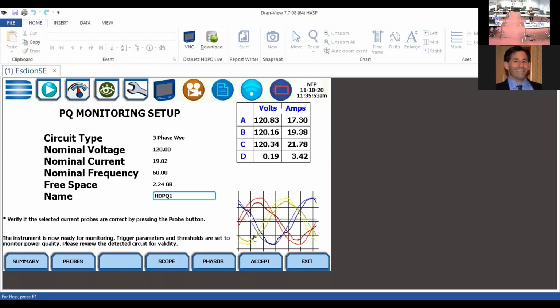And of course, there's another way as well — you can use the phasor display. If I click on phasor, I can see it from a phasor perspective. Looking at phase A here, which is our voltage vector and current vector, represented by voltage A and IA — if I had a reverse CT or reverse current probe, this would be 180 degrees out. So there's a very easy way of determining if you're connected properly.